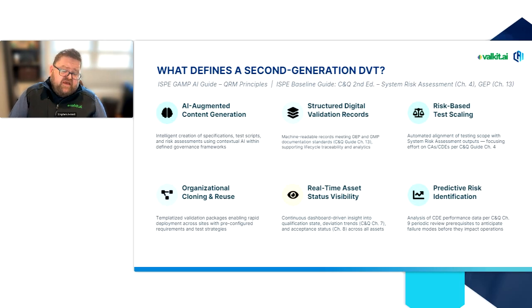Scope and visibility: risk-based testing at scale automates what used to be a manual judgment call. How much testing does a system actually require? Having a risk-based testing engine allows testing scope to be driven by risk. You're testing things that have a direct effect on product quality and patient safety, and you can meter the testing based on the impact of specific specifications. Scale and prediction: the ability to reuse templates and master data management. The second facility that you stand up doesn't have to start from scratch. You have predefined, pre-configured packages and pre-qualified requirements, dramatically reducing deployment time. Predictive risk identification means you're not waiting for periodic review to find out a system is trending towards a requalification event. CDE performance data can tell you have a problem before it becomes one.